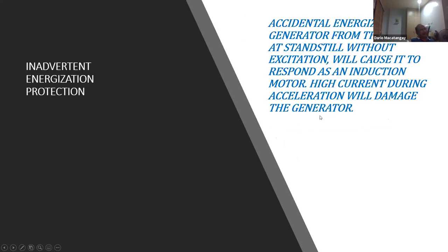Inadvertent energization protection. This is accidental energization of the generator from the system at standstill. Let's say you're doing a maintenance shutdown, it's offline, and then suddenly the breaker closes. You energize the generator at standstill, and it becomes an induction motor. High current during acceleration will damage the generator.